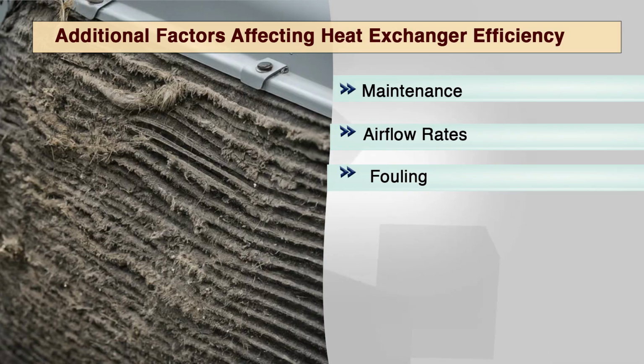Then we will discuss fouling. Fouling refers to the buildup of unwanted materials on the heat exchanger surfaces. This can be caused by mineral deposits in water or chemical contaminants in air streams. Fouling acts like an insulator, hindering heat transfer. Proper material selection for the heat exchanger and the fluid it handles can help mitigate fouling issues. By considering these additional factors alongside design and material selections, building designers and operators can ensure heat exchangers deliver on their promise of significant energy savings and a more sustainable built environment.